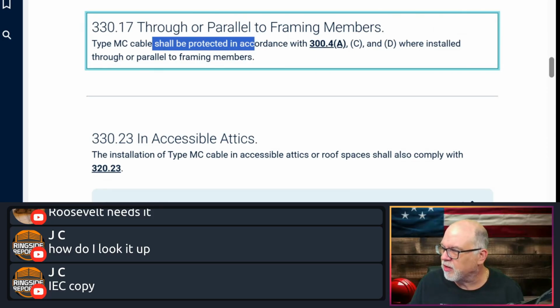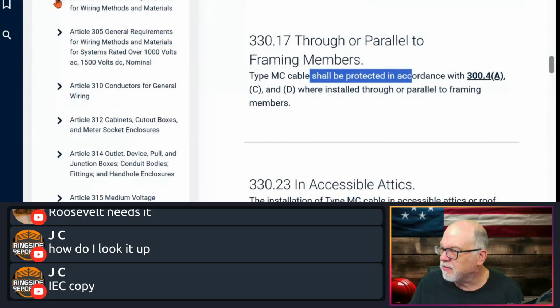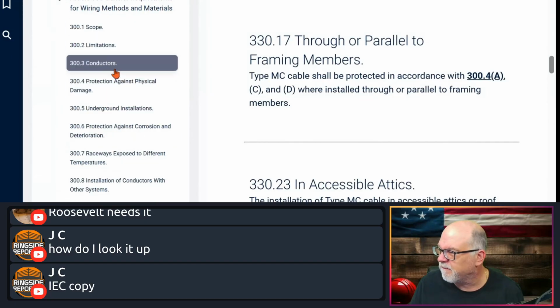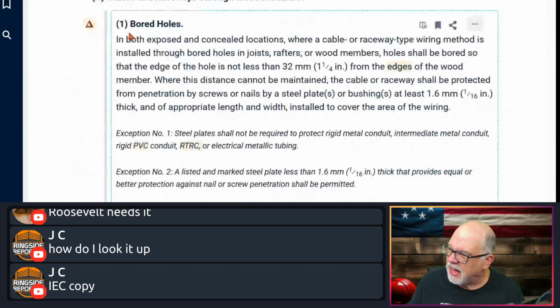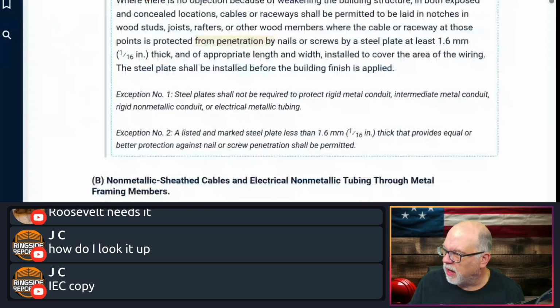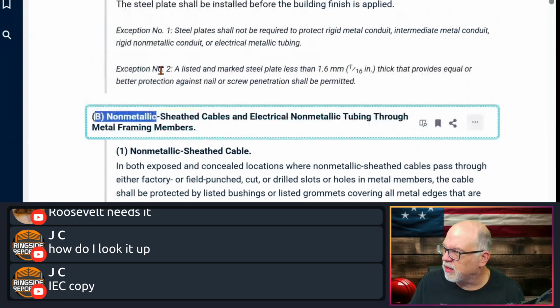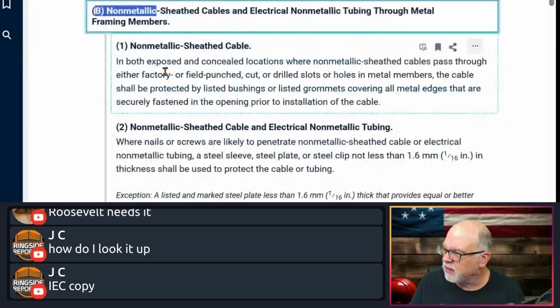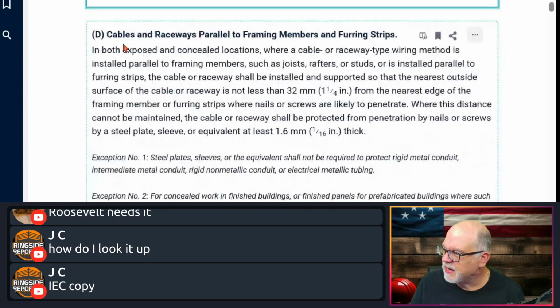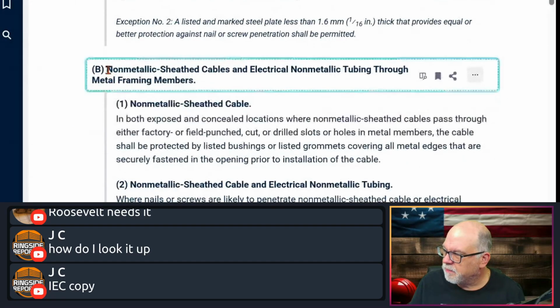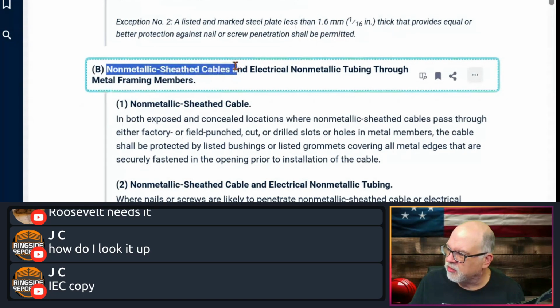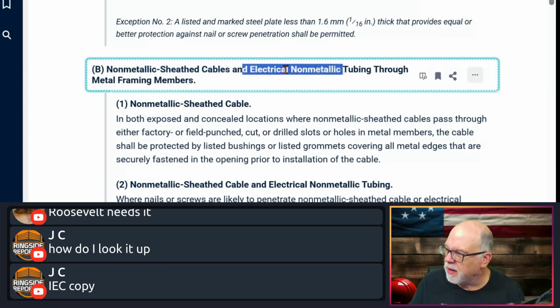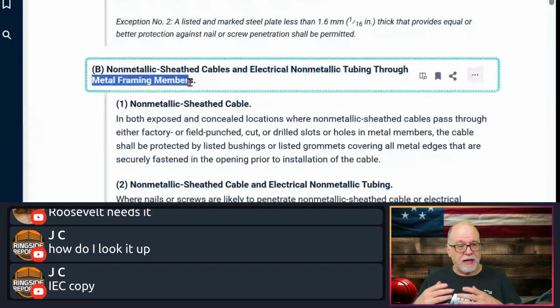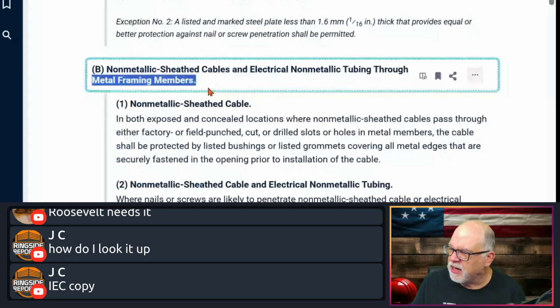Okay. Now this is interesting. I'll take you real quick to 300.4 because I do want to show you the differences in these real quick. So you see A is bored holes. And then notches. You notice B isn't on the list, right? It was C and then D. But you know why B is not on it? Because B is specific to non-metallic sheath cable and electrical non-metallic tubing. Running through metal framing members is not an issue for MC running through metal framing members. It is for non-metallic and electrical non-metallic tubing through framing members.